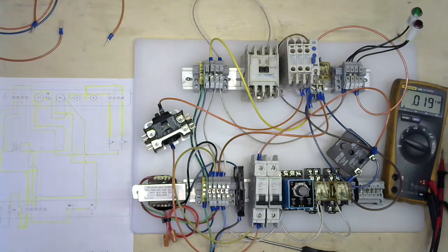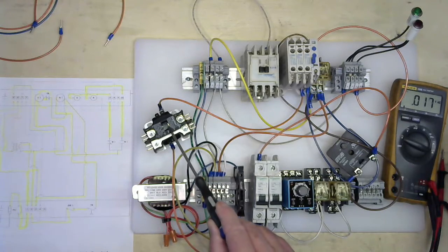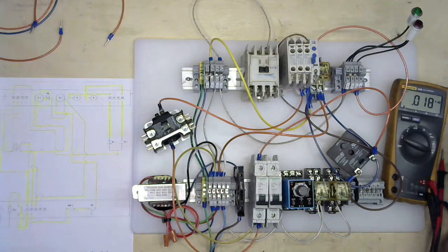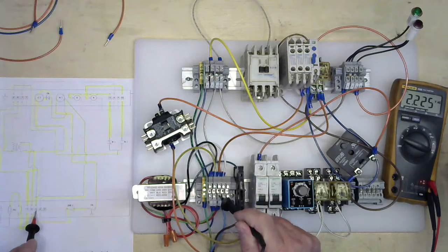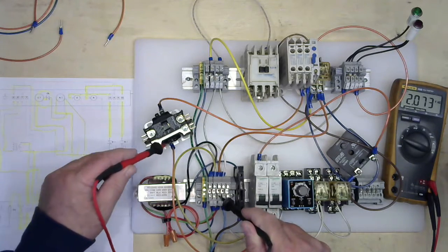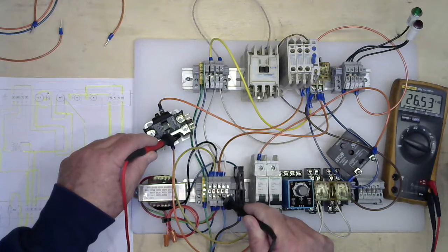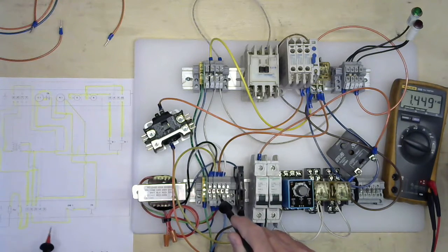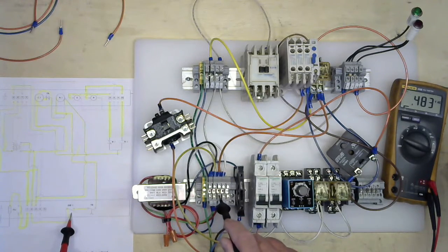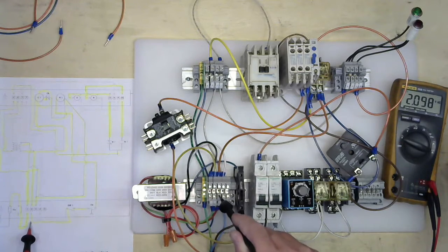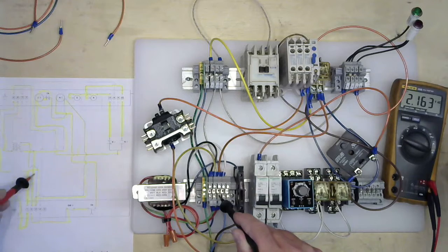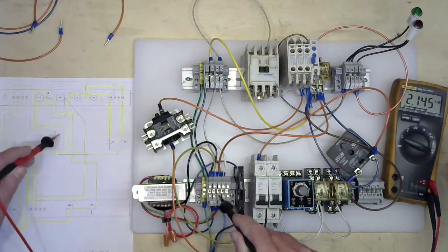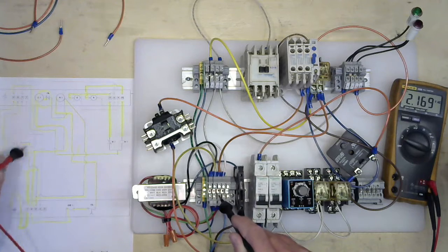As soon as I power the trainer up, my contactor here, you heard it click, just closed. To verify that, looking at the schematic, I know terminal 3 is my negative for 24 volts. If I check that across my contactor, I'm getting power. So I know from terminal 3, power is going to 2, into the switch here for the contactor. We have it come in here, always getting power. So unless I break power here, nothing is going to turn off C1.